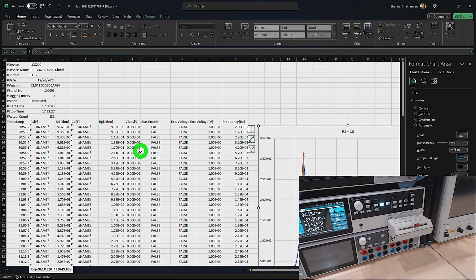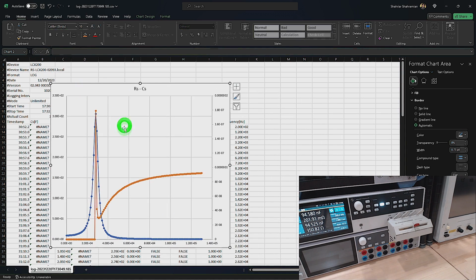And here's the result that the instrument created, a CSV file, and I've gone ahead and plotted everything to make it a little bit easier. The orange line here is the capacitance. If you look up until around this frequency, you cannot measure the capacitance, and all of a sudden you get a very large value of capacitance, then it drops, and then asymptotically approaches a constant value. And the blue is RS in this case. If I hover over here with the mouse, you can see the frequency is 28.2 kilohertz. That's exactly the resonance frequency of this LC combination. And at the tail end of the capacitance, we're approaching 92 nanofarad or so.